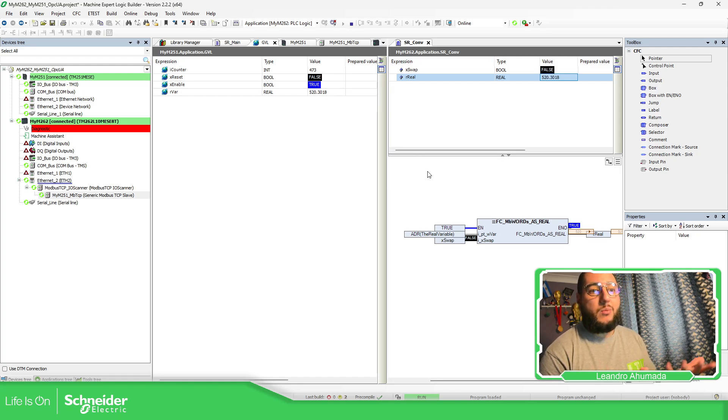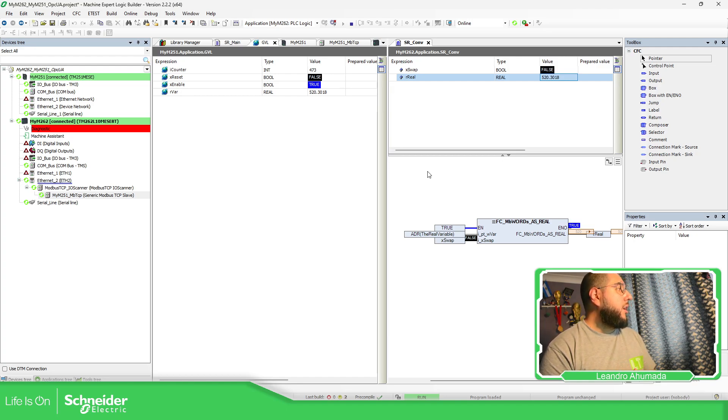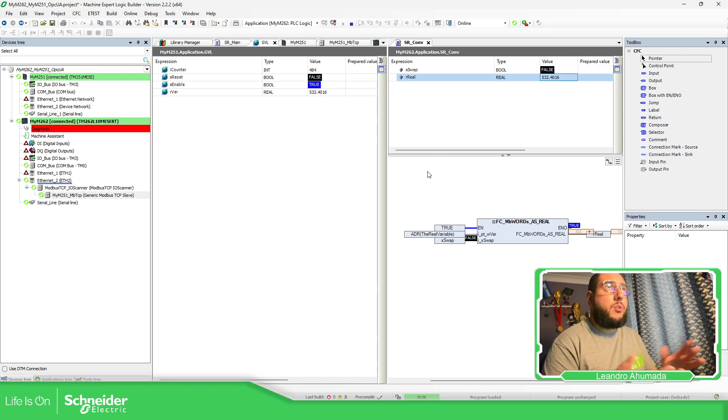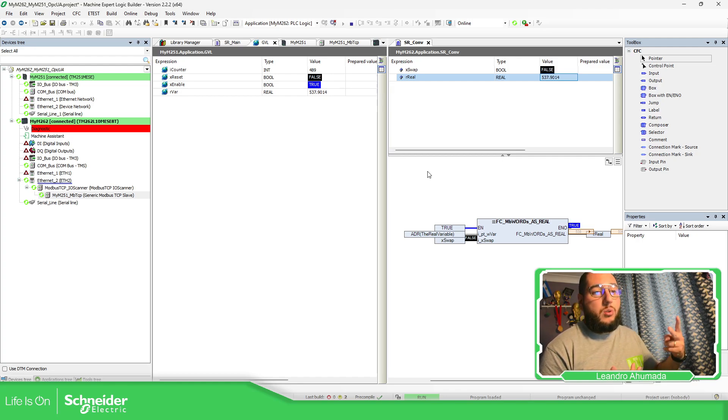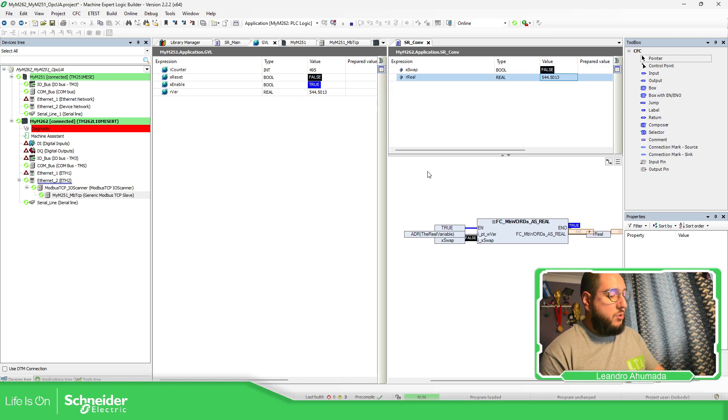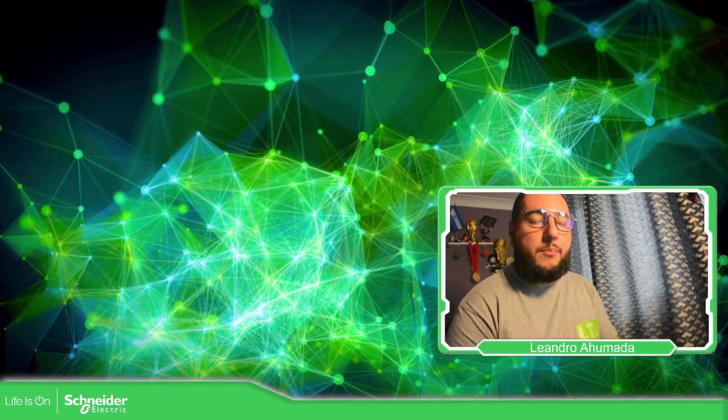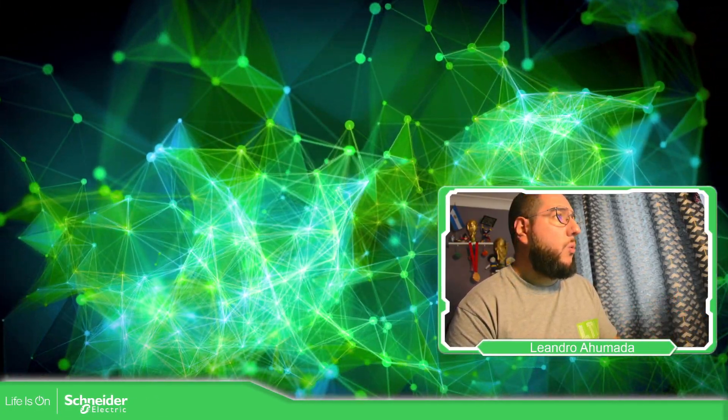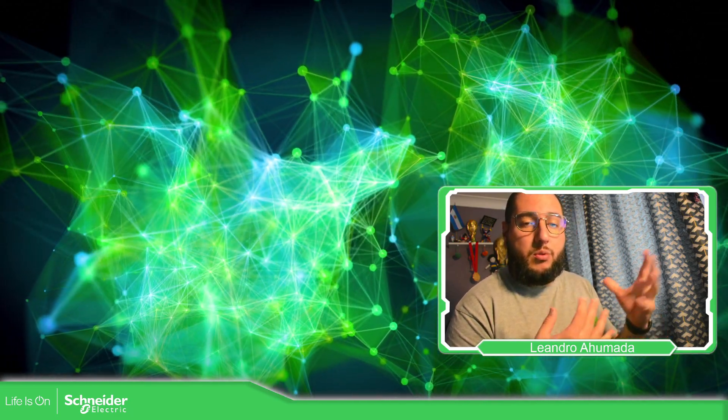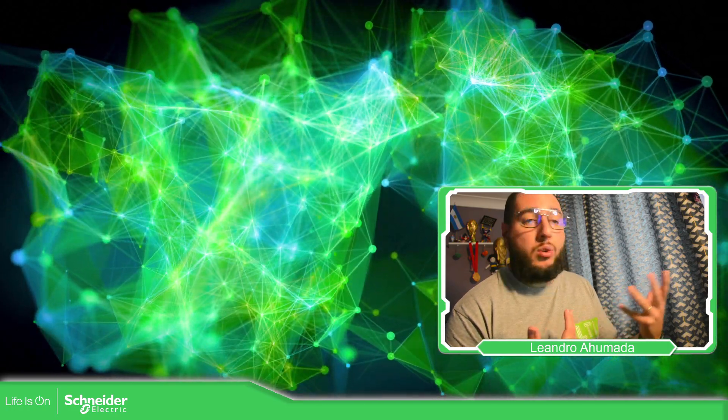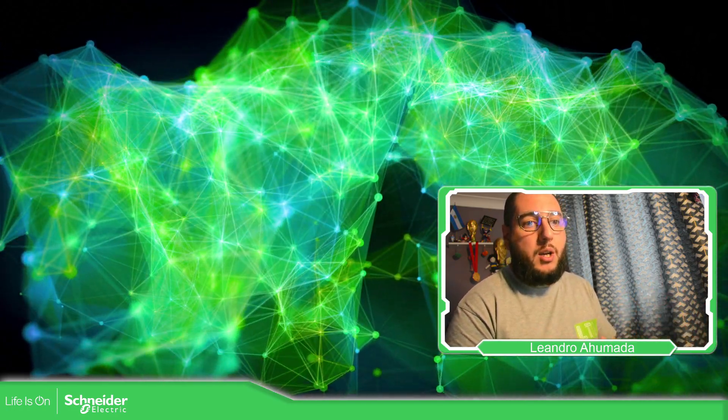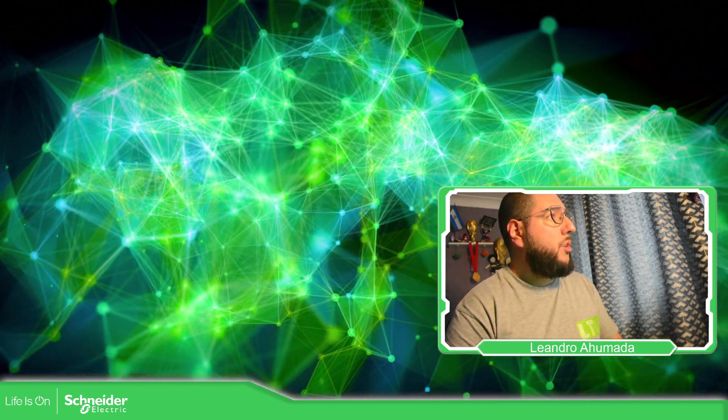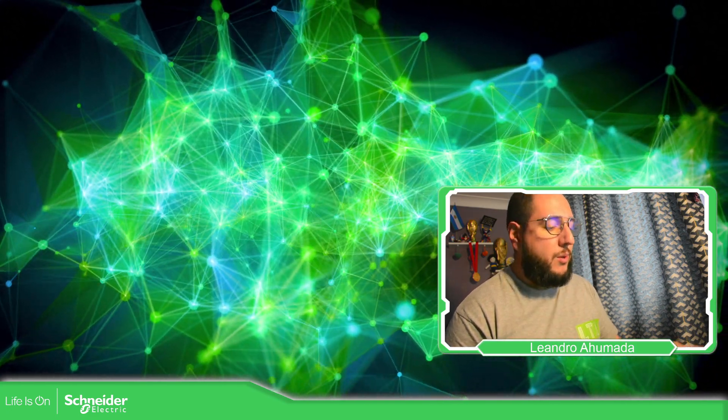This is just one way using the library that I can share on the link. So this is how you can read real variables on slaves or servers on Modbus TCP or Modbus serial communication. Just read the two continuous registers, add the ADR on the input, and then that should be it to get the real value that you are after. You will need the library in case you want to use this function block, otherwise you will need to use pointers, but I'm going to explain how to make the pointers. Thank you very much for watching this video and I'll see you on the next one.